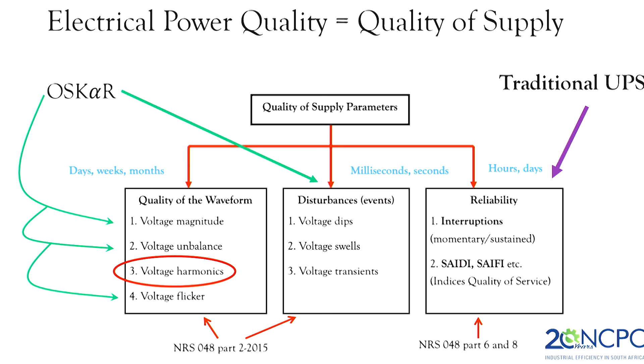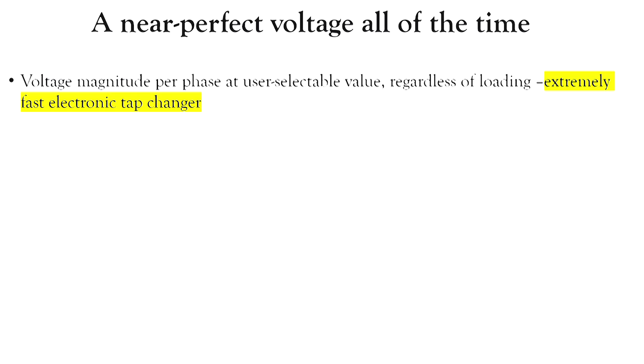The idea is that we can now, with the technology being available from Germany, as I have already mentioned or hinted towards, serve any load with a perfect voltage magnitude, regardless of loading. No voltage drop should concern you in the supply network. Regardless of the variations in the supply network, acting as an extremely fast tap changer, at least 10% above and below the nominal value.